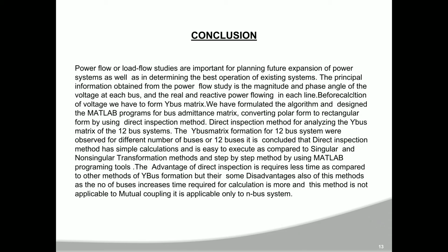Power flow or load flow studies are important for planning future expansion of power systems as well as for determining the best operation of existing systems. The principal information obtained from the power flow study is the magnitude and phase angle of the voltage at each bus and the real and reactive power flowing in each line. Before calculation of voltage, we have to form the Y-bus matrix.